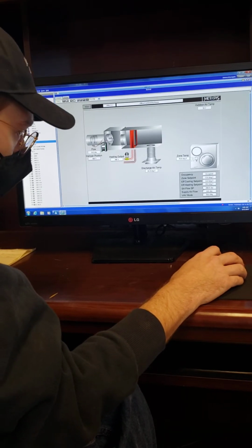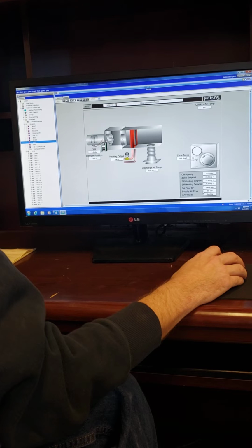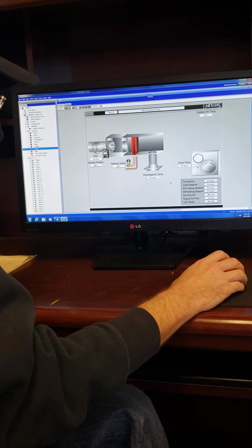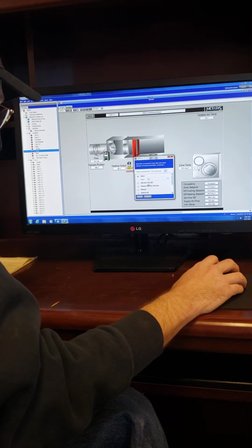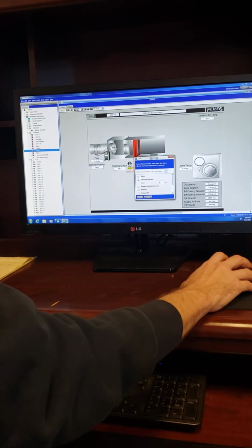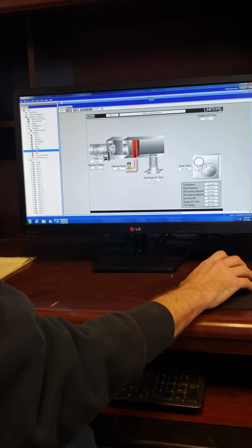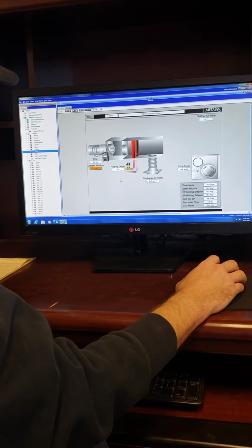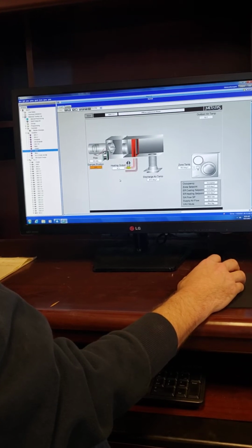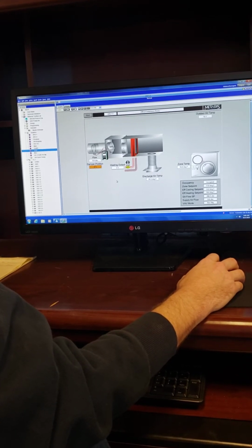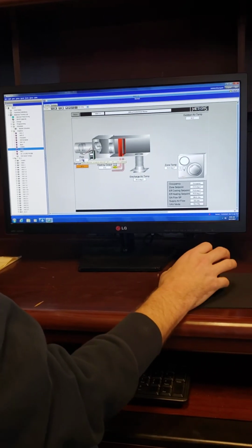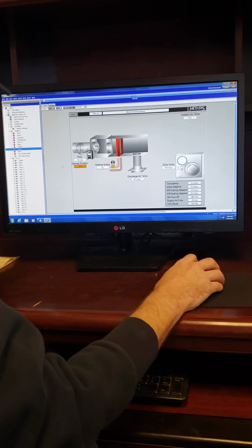Actually, I don't hear anything. It's very quiet, minimal. Before we opened it, it was quiet. Now, no, I don't hear it. But usually I hear it. I'll take a look at the unit and see maybe if the damper's slipping. Yeah, no change in flow. That's fine. I'll run and grab my ladder and pop my head in the ceiling real quick.